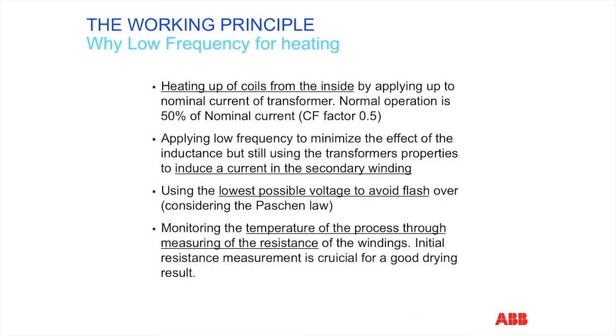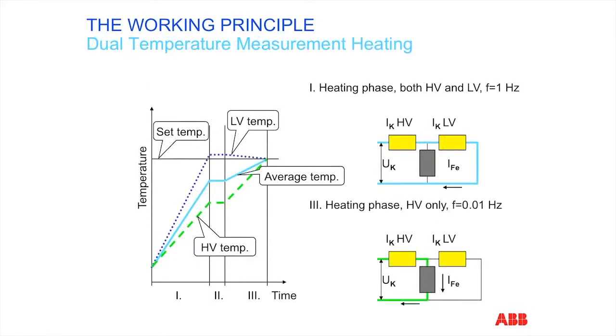The ABB system is capable of determining the temperature of the windings by determining the relationship between winding temperature and its resistance. This is not a trivial capability and helps to ensure that safe winding temperatures are not exceeded. The choice of frequency will determine whether or not both the HV and LV windings are heated, or only the high-voltage winding.